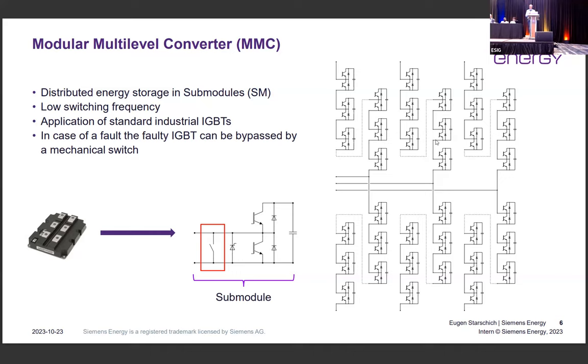That means, and this is the submodule that you see here, we break up the big central converter with many IGBTs in series and divide it into small pieces, and each piece is called a submodule. By this division into small pieces, we have a completely different approach. First of all, we can use standard industrial IGBTs. In case of a fault, which was the main design criterion previously, instead of having IGBT fail-safe capability, we now have a mechanical switch, as shown here, which can create a bypass. And this was the crucial change in the complete design of the converters.